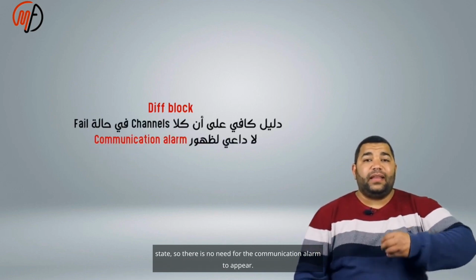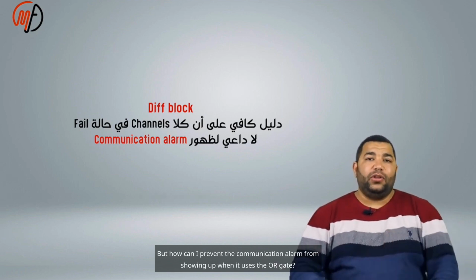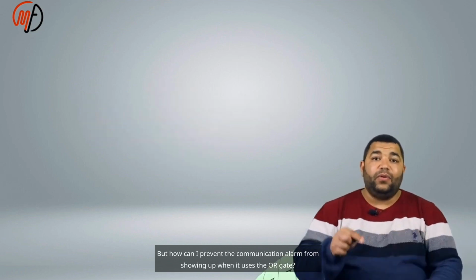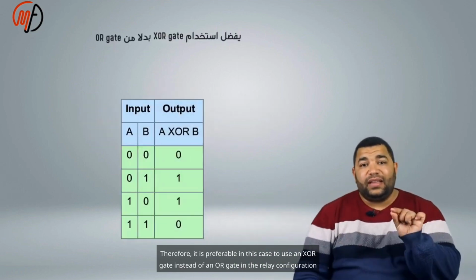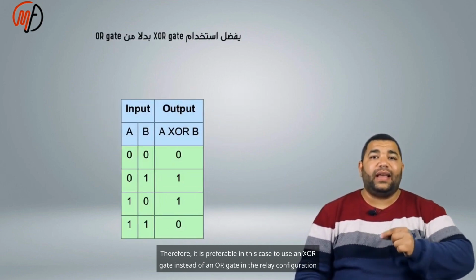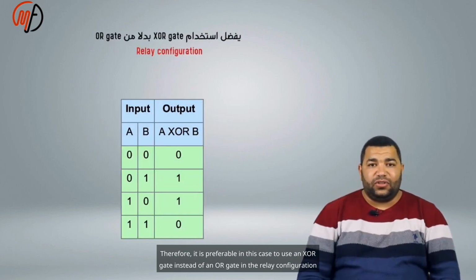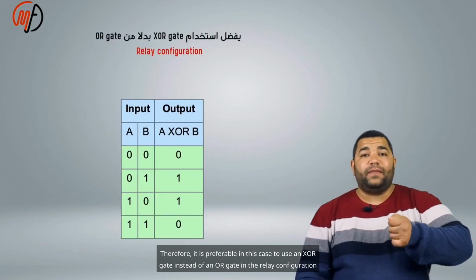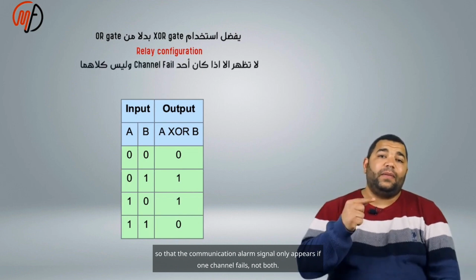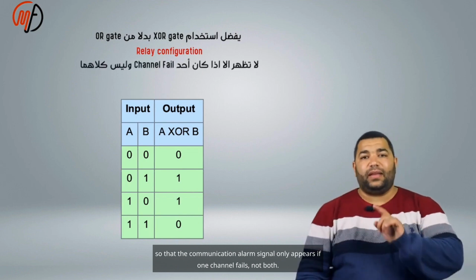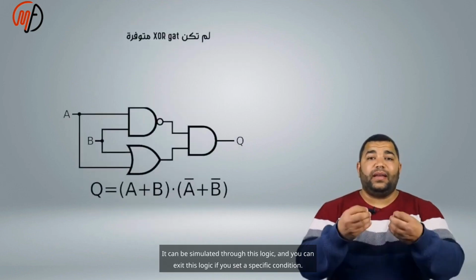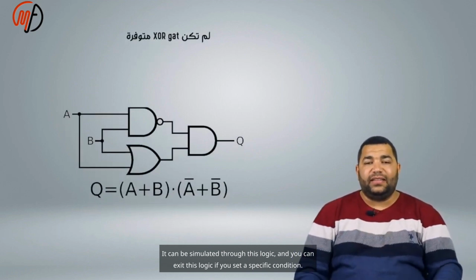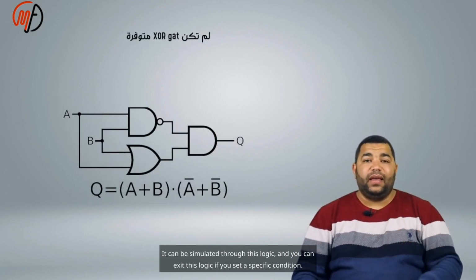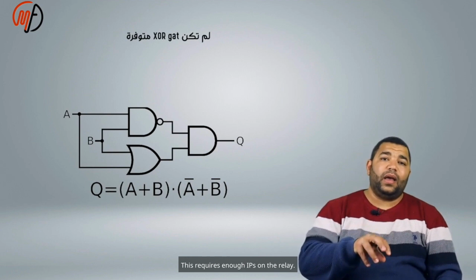But how can I prevent the communication alarm from showing up when it uses the OR gate? Therefore, it is preferable in this case to use an XOR gate instead of an OR gate in the relay configuration, so that the communication alarm signal only appears if one channel fails, not both. It can be simulated through this logic, and you can exit this logic if you set a specific condition. This requires enough IPs on the relay.